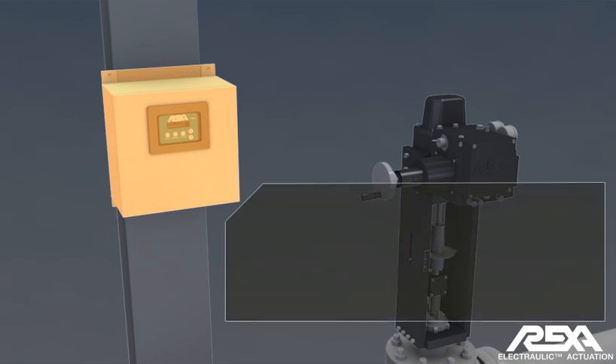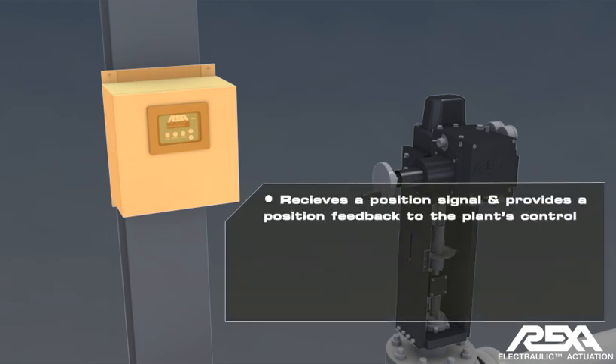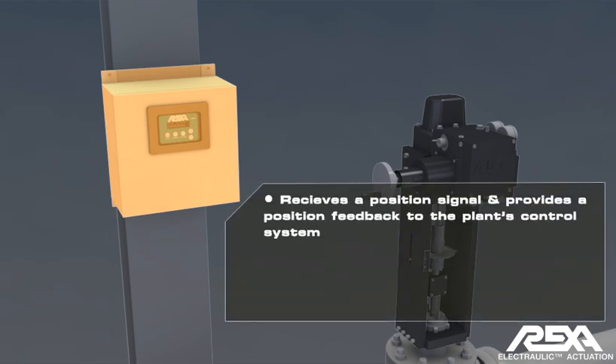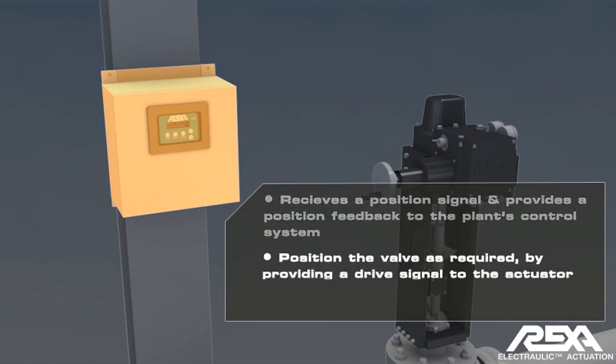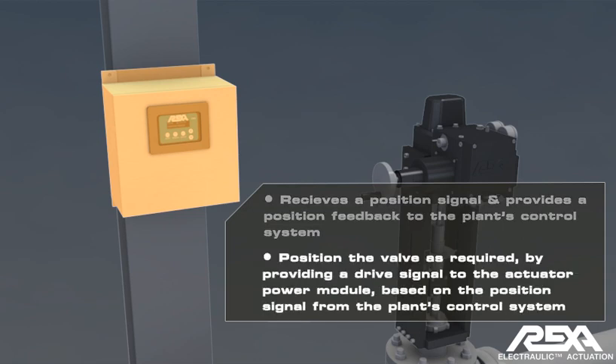The control enclosure receives a position signal and provides position feedback to the plant's control system. Its other function is to position the valve as required by providing a drive signal to the actuator power module based on the position signal from the plant's control system compared to position feedback from the actuator's cylinder.